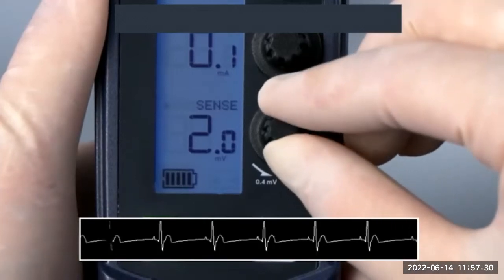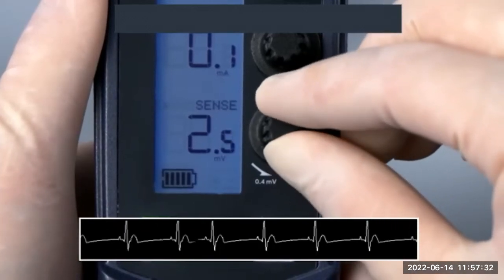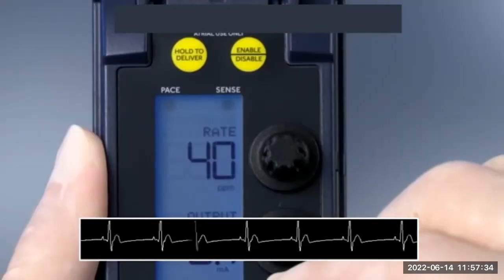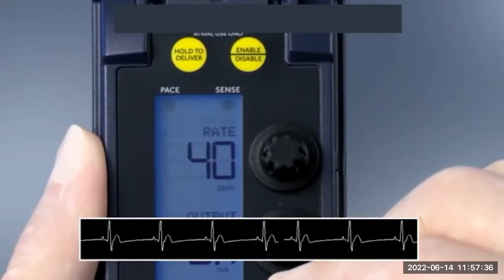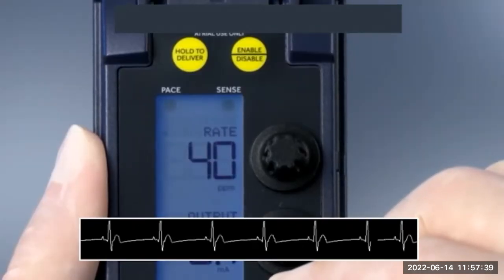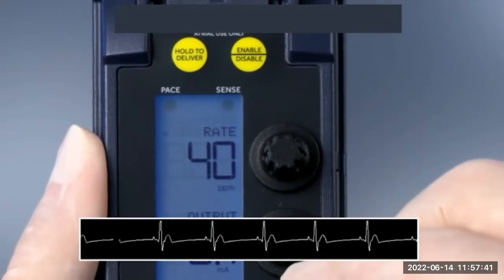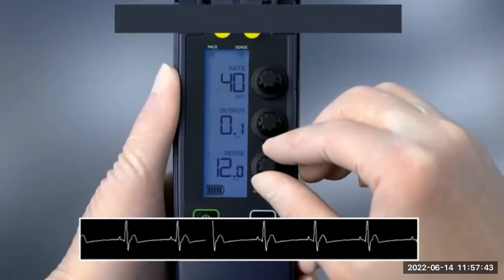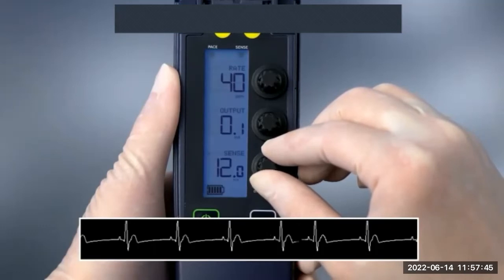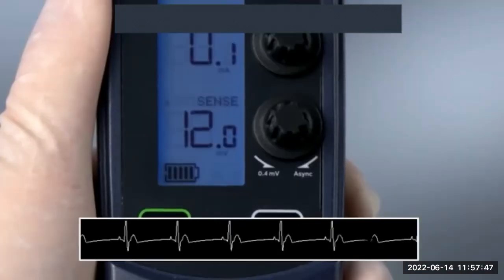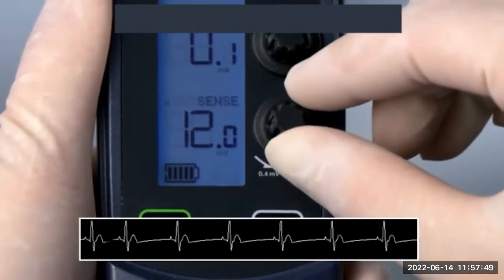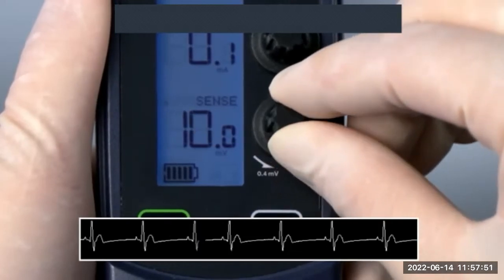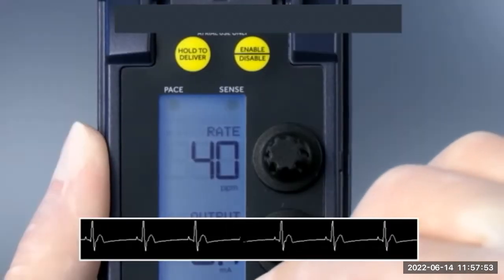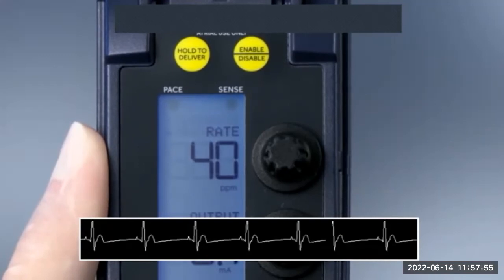Slowly turn the sensitivity dial clockwise, which increases the millivolt value, until the sense indicator stops flashing. The pace indicator flashes continuously, but capture is not likely because the output value is set to the minimum. Next, increase the sensitivity by slowly turning the dial counterclockwise, which decreases the millivolt value, until the sense indicator starts flashing. The pace indicator then stops flashing.